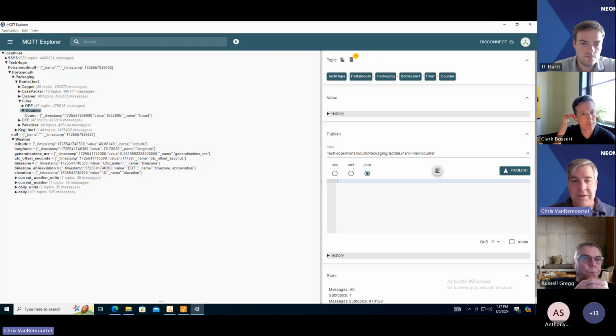You could have brokers that are site-specific, just worry about a site, then push up to an enterprise broker. One thing I really like about MQTT, for scalability, is that OPC is polling based. If you ask the PLC every second what's the set point, that's a lot of wasted CPU cycles. We've run into problems at sites where we're overloading the PLC, not because of the logic it's doing, but the comms. Nirvana, in my mind, is when a PLC can publish changes to a broker and only publish changes. Then the broker has the most current data, and the PLC is only doing stuff when it needs to, not overloaded by 5 different clients asking it the same question.